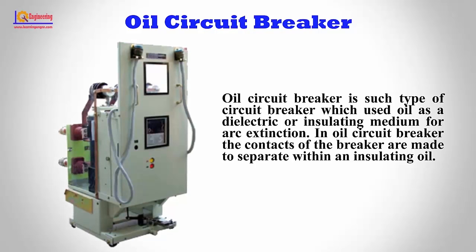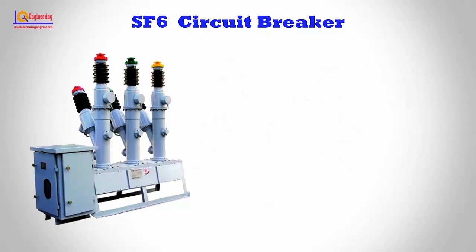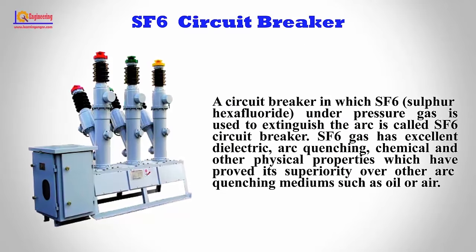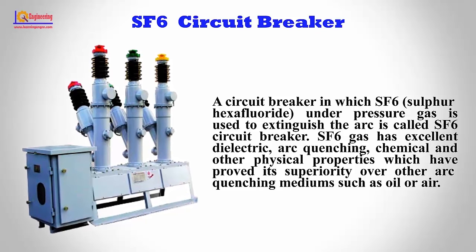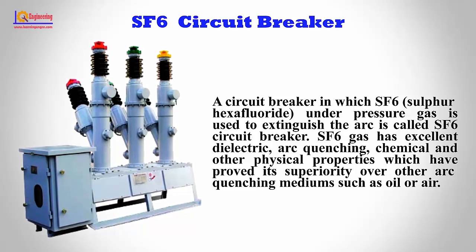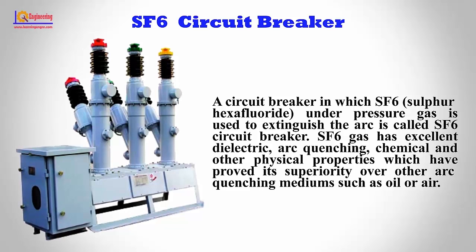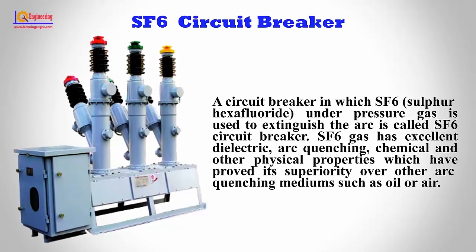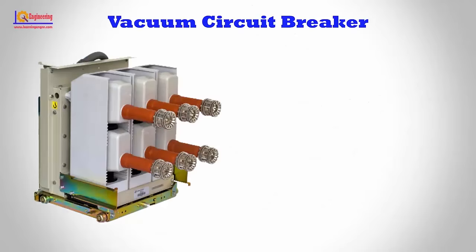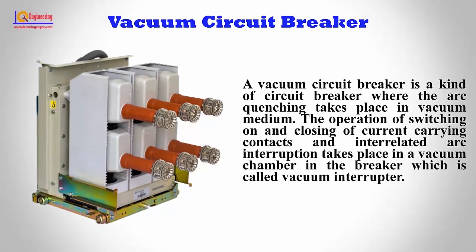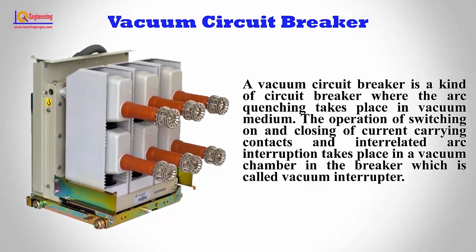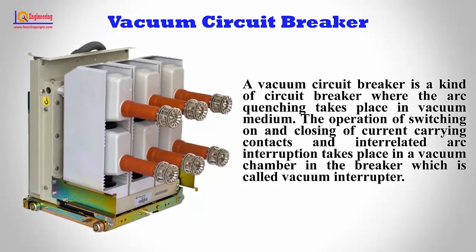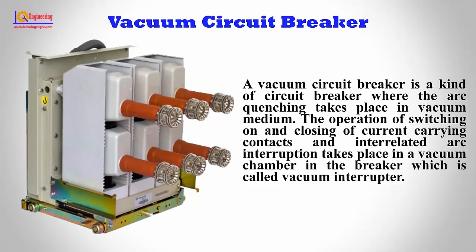In an Oil Circuit Breaker, the contacts of the breaker are made to separate within an insulating oil. In an SF-6 Circuit Breaker, SF-6 gas under pressure is used to extinguish the arc. SF-6 gas has excellent dielectric, arc quenching, chemical, and physical properties which have proved its superiority over other arc quenching mediums such as oil or air. In a Vacuum Circuit Breaker, arc quenching takes place in a vacuum medium; the switching and arc interruption occur inside a vacuum chamber called a vacuum interrupter.